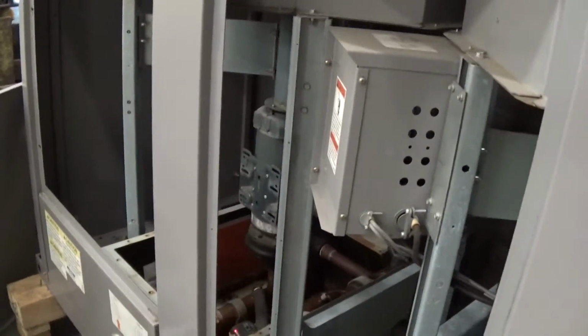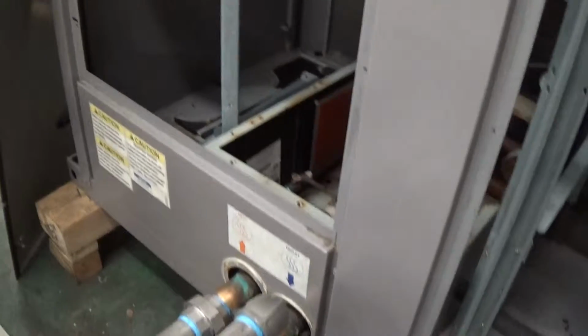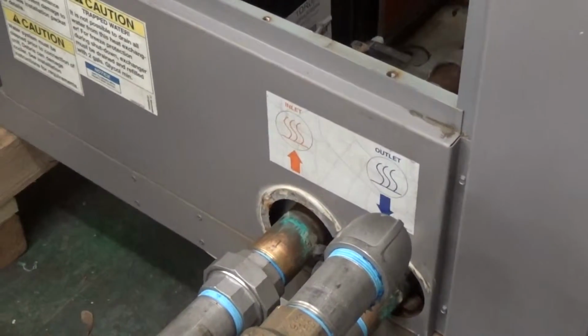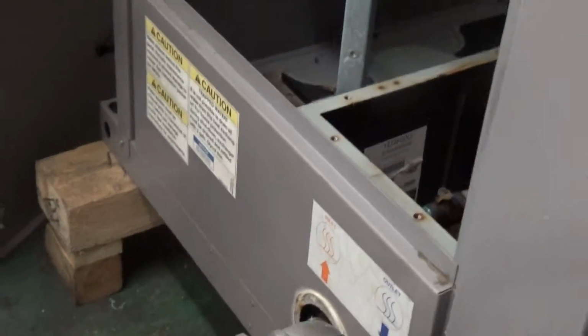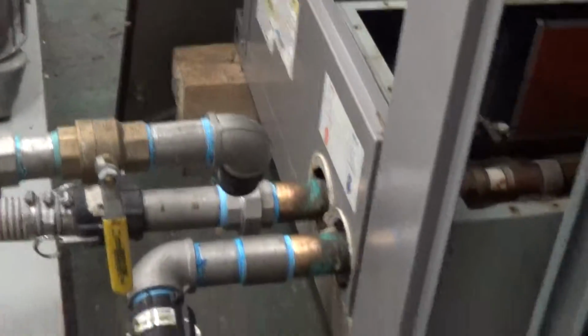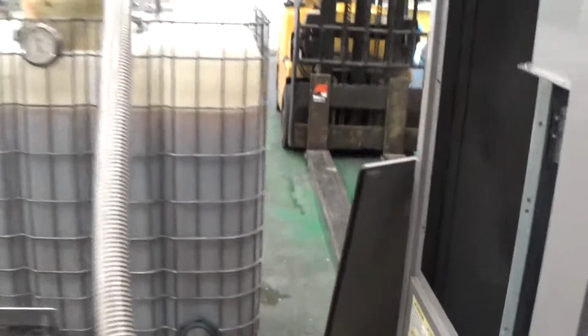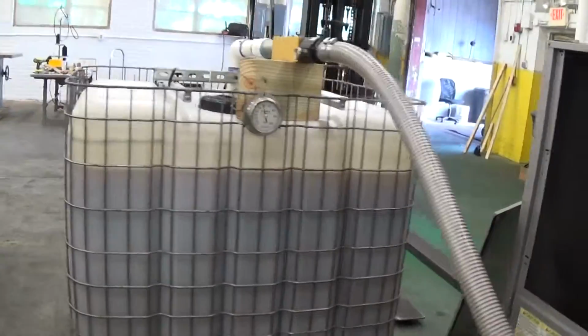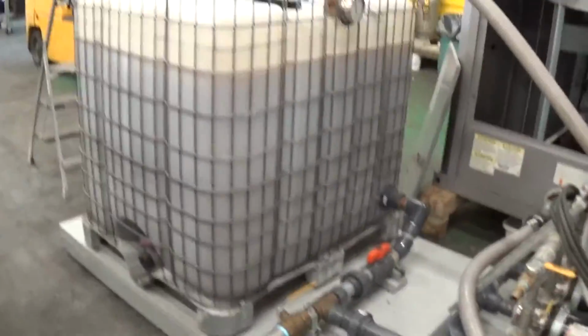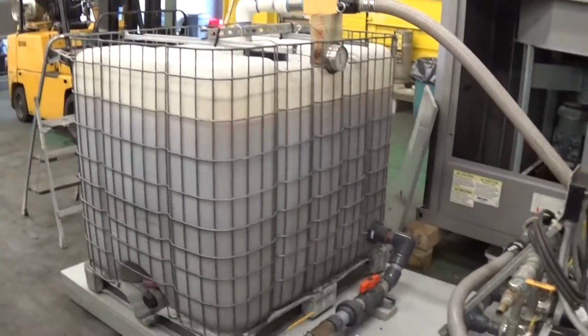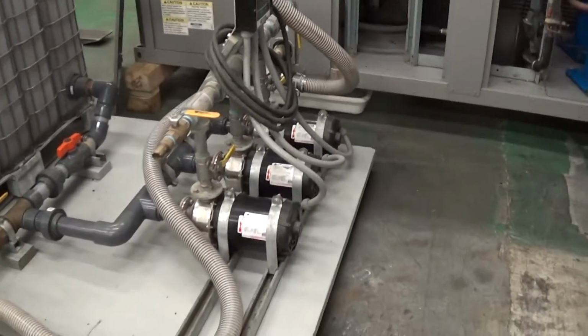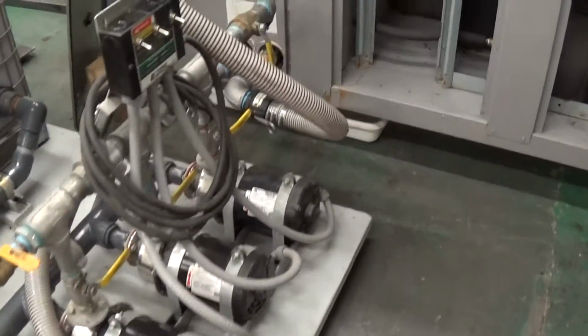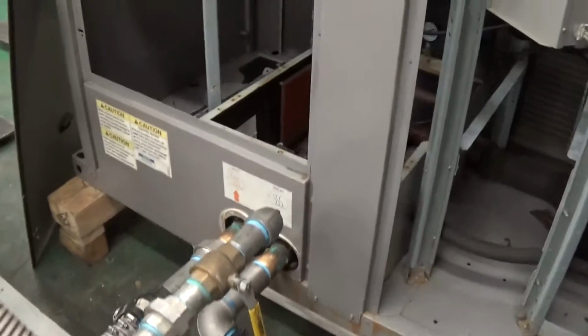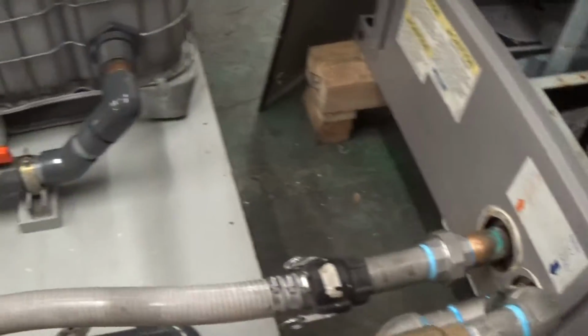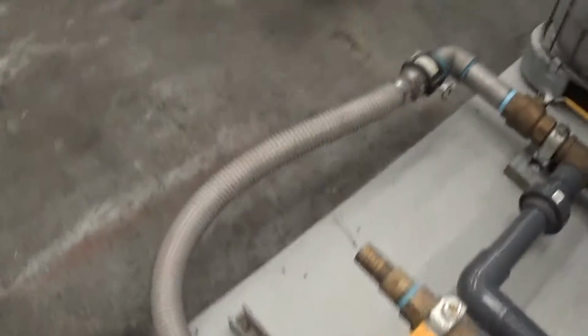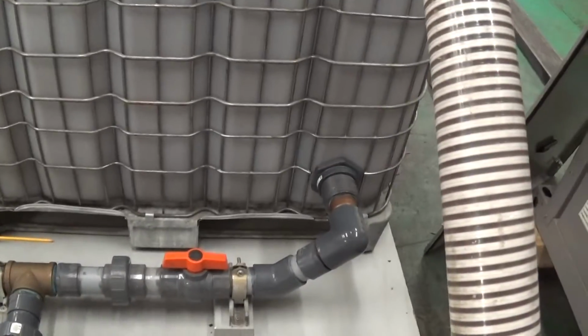So again, we have our own pump here. The inlet is effectively, I don't know, 6 inches off what will be the ground. We have it on blocks here in the shop, and we have it connected to our own about 280 gallons of glycol mix here on our test station. Because we're using the chiller's own pumps, we don't have to use any of our test pumps. So that's our inlet, which goes right back to the outlet of the tank.